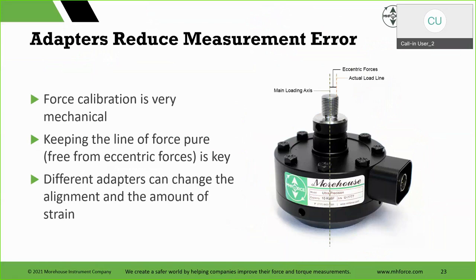And I said earlier, the eccentric force. If we look at this, the main loading axis, anything that's not center is eccentric, right? It's a force that shouldn't be there. The actual load line, maybe if you use wrong adapters or your tech doesn't use an alignment plug or some other things for the best alignment in these machines, or you have an out alignment condition using a testing machine and someone's just visually doing it, you might have, you know, a quarter inch. That's probably really exaggerating. You might have an eighth of an inch, a 16th of an inch misalignment, and that's going to throw some errors depending on the instrument.